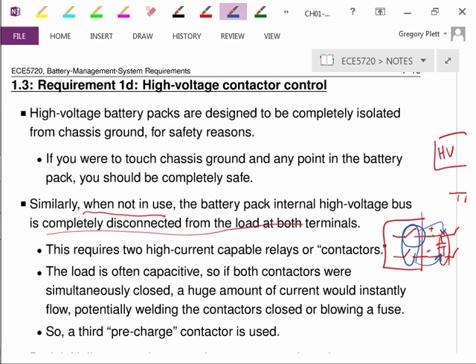So the simple thing of just closing a switch doesn't work. We need a different approach, or a refined approach. What we end up doing is using a third relay, or a third contactor, called a pre-charge contactor. The focus of this section of notes is to go through the steps of how you connect the battery pack to the load using this pre-charge contactor.